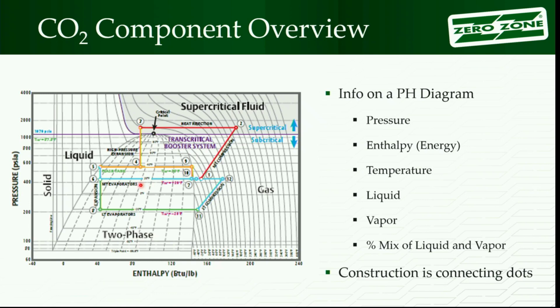If I start out over here and I measured it, I'm going to have more liquid by weight than I am vapor. If I'm on the right-hand side, I'm going to have more vapor than liquid. And it's pretty important because as we look at the representation, we're going to want to know what that percentage is. It explains why a gas valve does what it does, why the software is making that change. So evaporators, it's kind of a point-to-point as you build these.